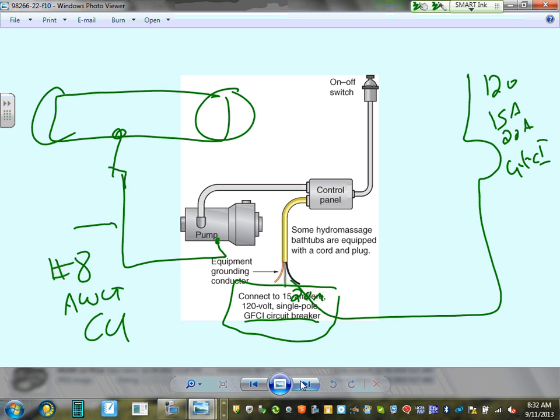So you protect the whole circuit, or you can put the GFCI breaker here, and this will most likely be a plug, a non-GFCI receptacle, just a regular receptacle, and that will be a GFCI breaker. So either a receptacle or a breaker would take care of you. But you can't have the GFCI receptacle right here because it's inaccessible, non-accessible. Any comments, guys? Any questions about the hydro massage bathtub? So that's basically what the hydro massage bathtub is.